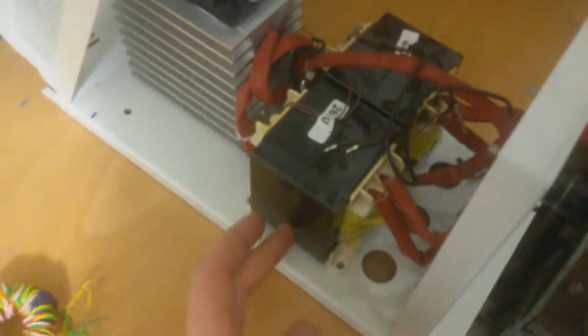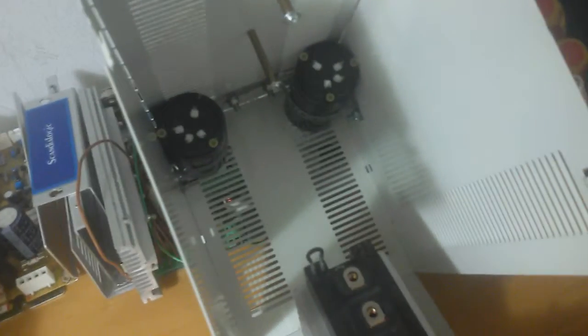Isolation transformer for output, these are big ferrite transformers. We'll step up the voltage slightly. I see those fat bus bars here, goes into those transformers, and we have those little thinner wires coming out, two pairs of them coming out of each one. So nearly 300 volts in, and that's almost nearly 600 volts out. It will be a half bridge, that's an IGBT, and there are the capacitors.